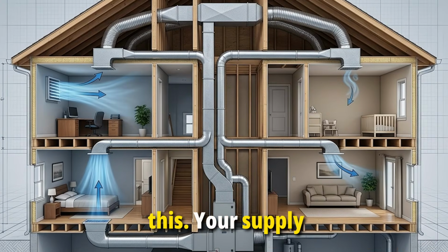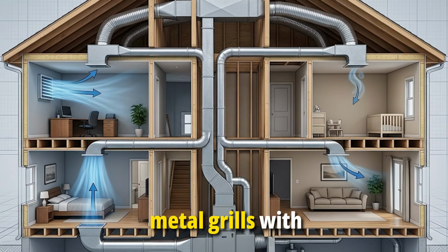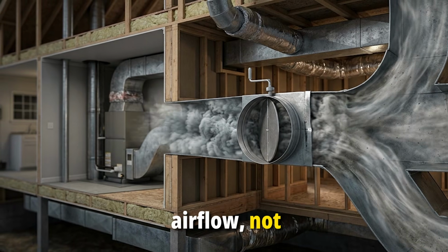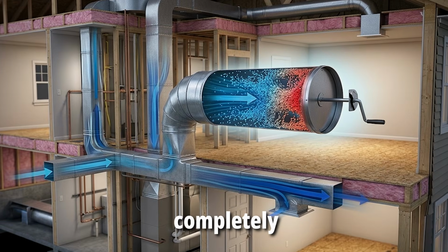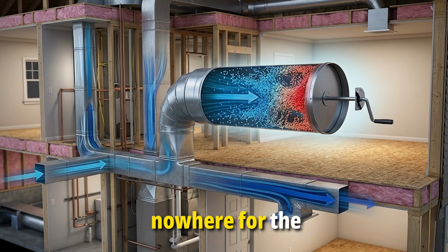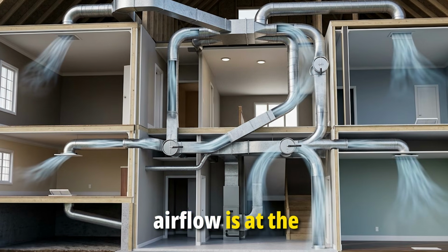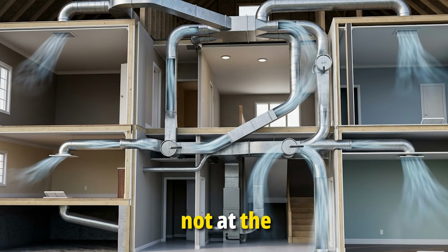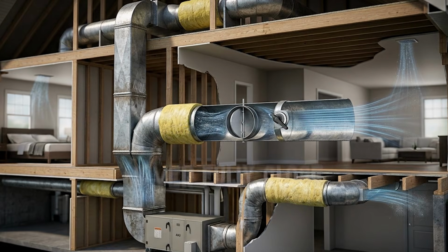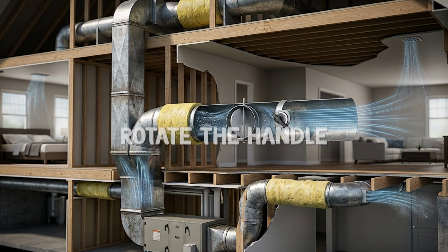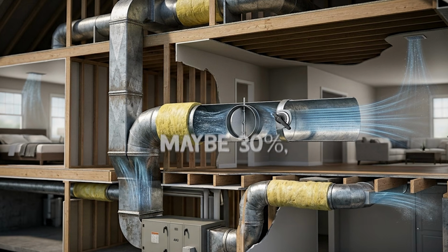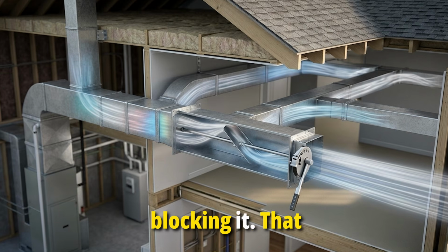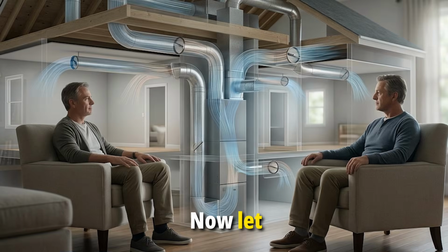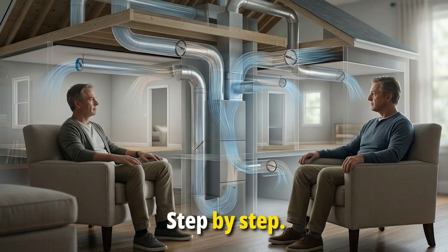There is also this, your supply registers, those metal grills with adjustable louvers on your floors and ceilings, are not dampers. They are for directing airflow, not controlling it. Closing them completely pressurizes the duct branch with nowhere for the pressure to go. The right place to control airflow is at the branch damper inside the duct, not at the register at the end of it. The rule is simple. Never fully close a damper. Restrict it. Rotate the handle about a quarter turn from fully open, maybe 30%, and stop there. You are throttling flow, not blocking it. That distinction matters. Now let me walk you through exactly how to do this, step by step.